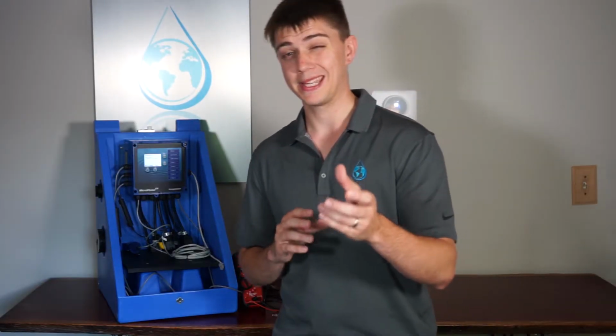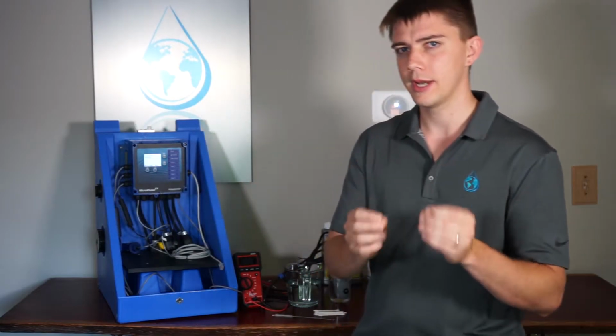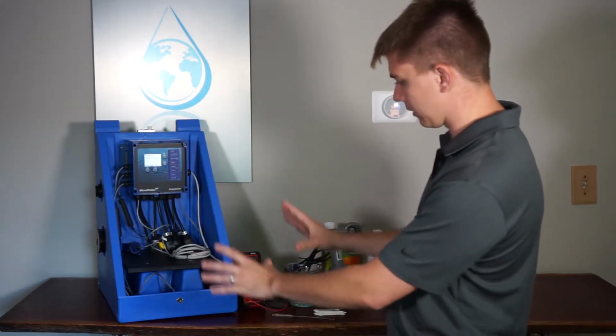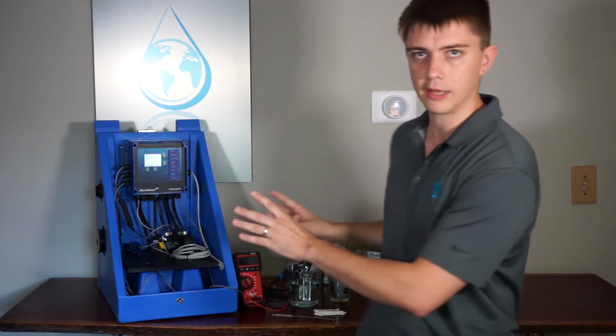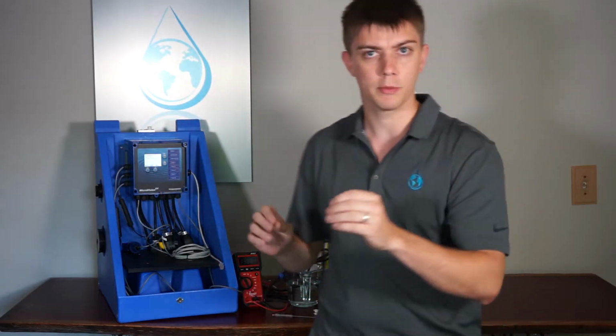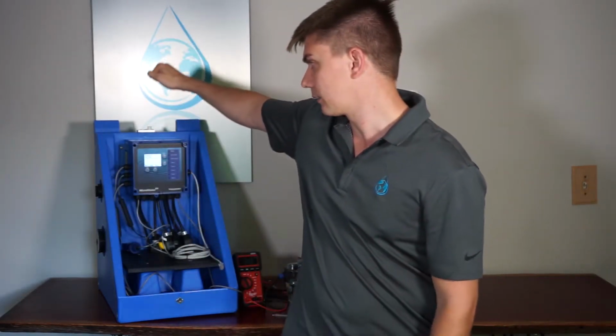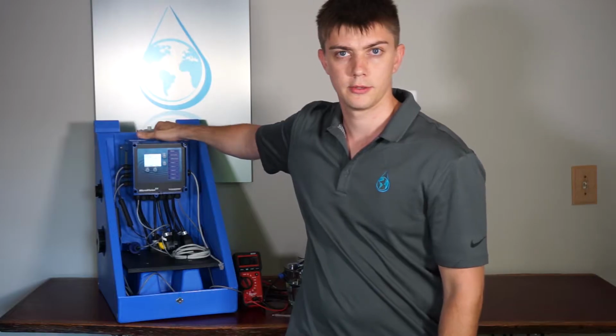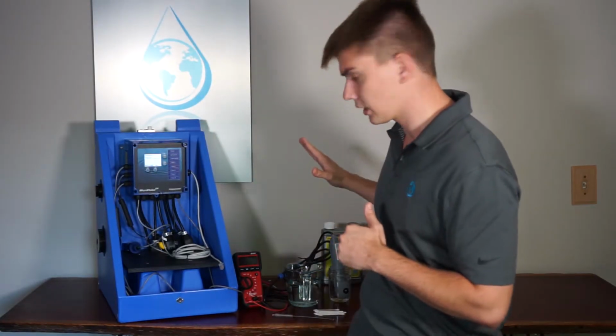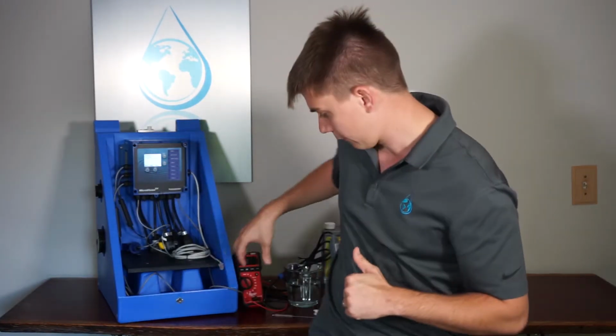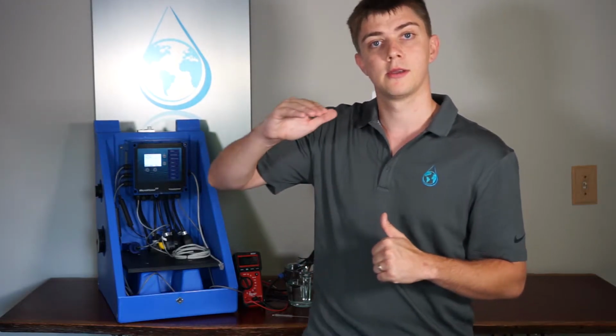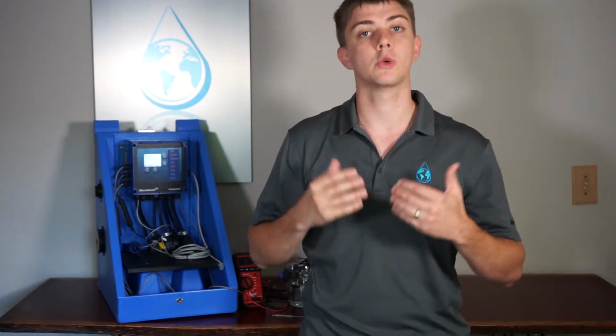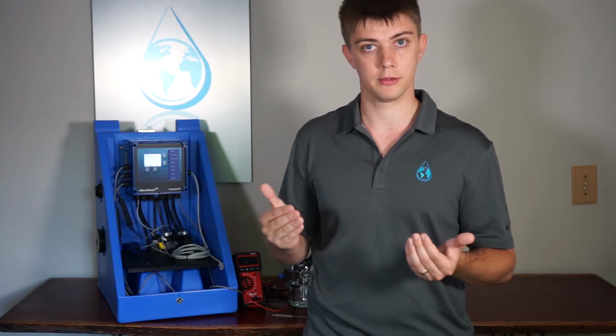Now that we've gone over what PTSA is and how it can help you, the next is to understand a little bit more about the actual installation to give you everything you need to avoid making some costly errors. So out of the box, this probe is going to be putting out a 4 to 20 milliamp signal tied to your controller. 4 milliamps out of the box is going to be 0 parts per billion of PTSA product. 20 milliamps is then going to be 200 parts per billion.